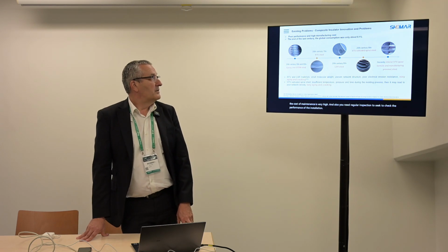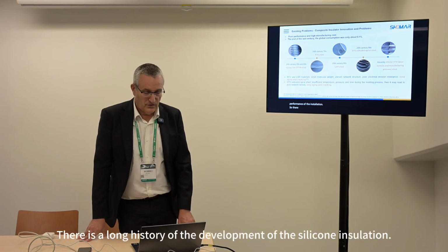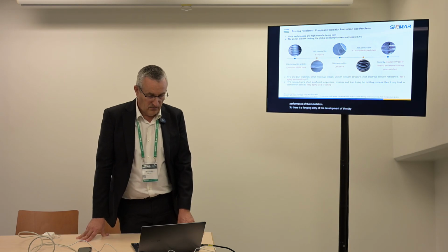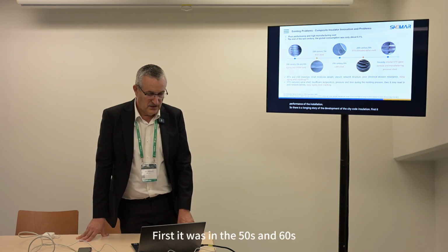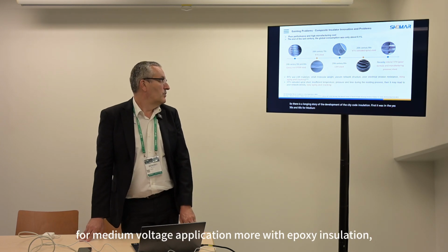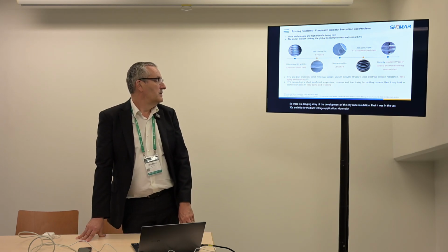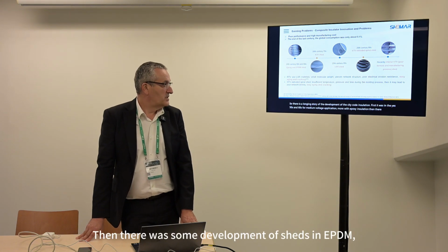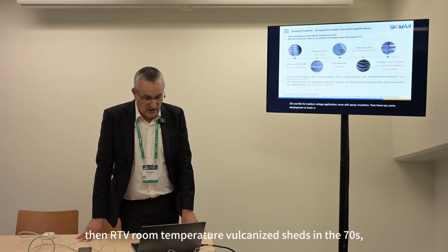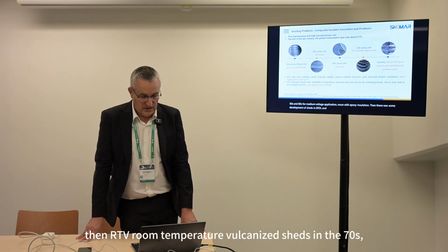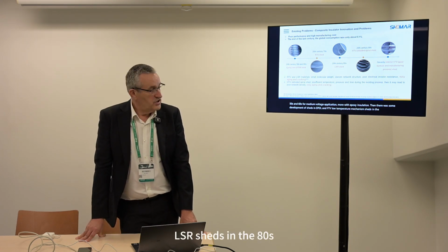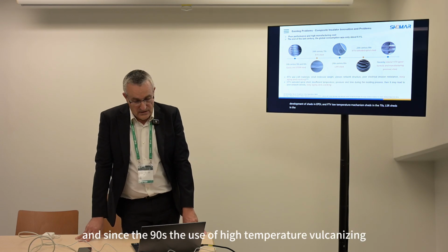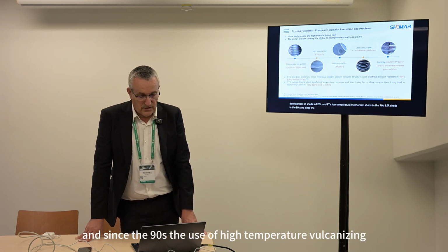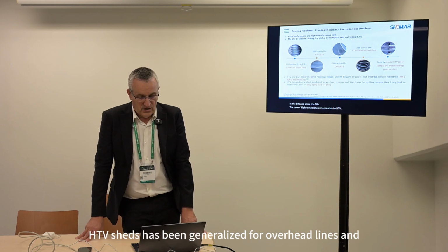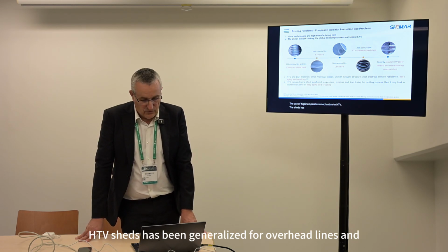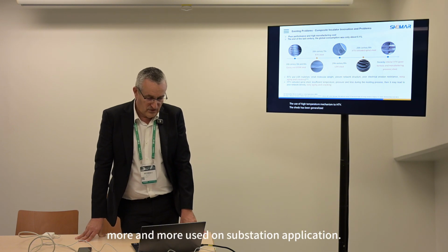So there is a long history of the development of silicone insulation. First, it was in the 50s and 60s for medium voltage application, more with epoxy insulation. Then there was some development of sheds in EPDM. Then RTV, room temperature vulcanizing sheds, in the 70s, LSR sheds in the 80s, and since the 90s, the use of high temperature vulcanizing, so HTV, sheds has been generalized for overhead lines and is used more in substation application.